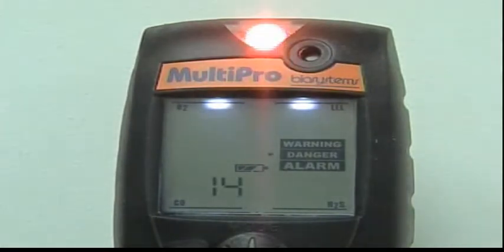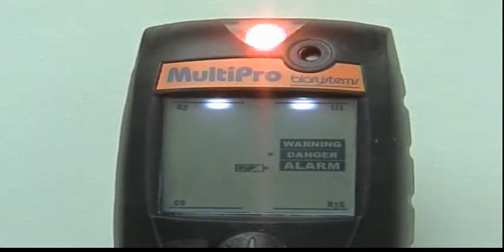It is not necessary to make a calibration adjustment if the readings are between 90% and 120% of the expected value as given on the label of the calibration gas cylinder. Readings between 90 and 120% are considered to be accurate, and it is safe to use the instrument without further adjustment. If the readings are considered inaccurate, then the instrument must be span calibrated before further use.